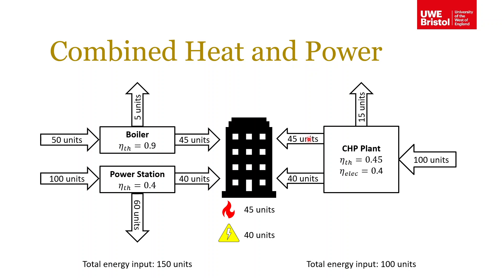I've perhaps been a bit naughty here showing the CHP plant as the only source of thermal energy and power to the building. In reality, when sizing a CHP plant, you will often need either top-up heat or top-up power from the grid depending on demand. There's an art to sizing CHP plants — you don't want it too big for its application, and equally you don't want it too small so that you need to access more top-up power and heat from the network.